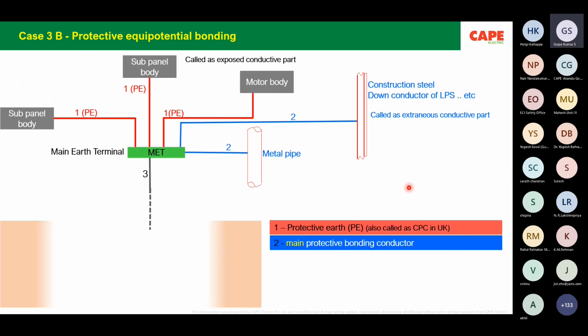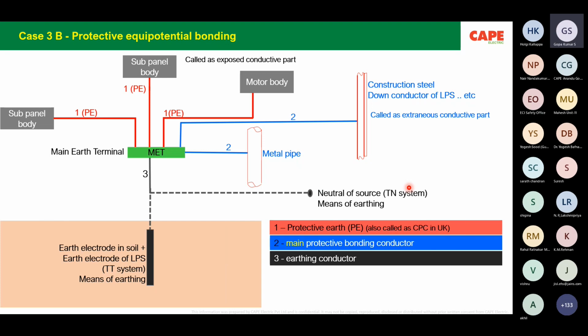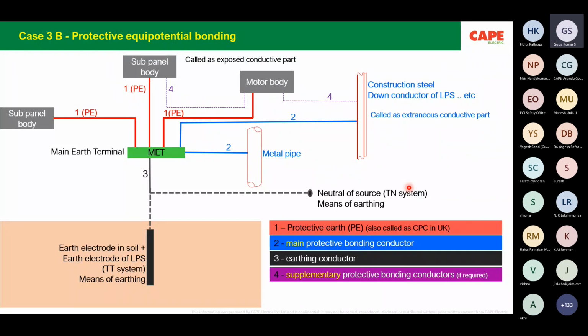So the second part of automatic disconnection is called protective equipotential bonding. I would say this is not the second part. If you look at the standard, what is written is that protection against shock is achieved by protective equipotential bonding and automatic disconnection of supply. So protective equipotential bonding is preceding, that is the first one. It means every metal part in your building must be interconnected in such a way that the potential difference allowed within the building during a fault condition is maximum 50 volt. So very much important, protective equipotential bonding.